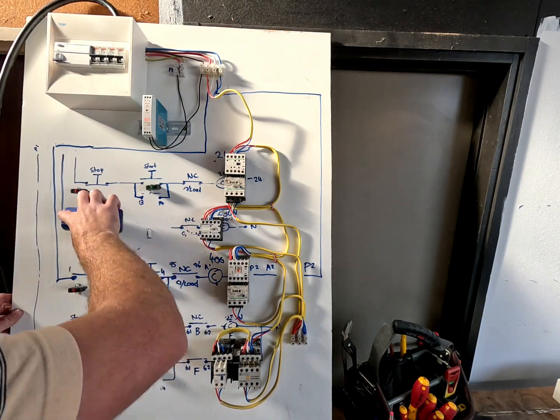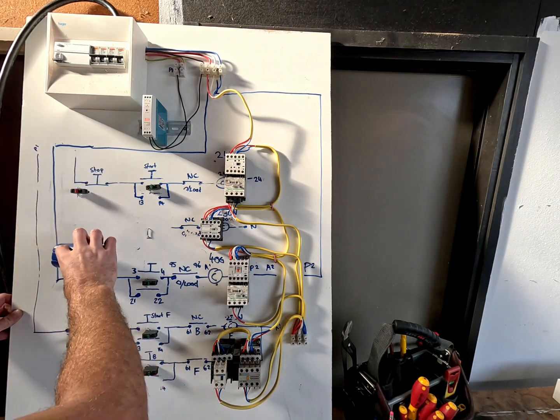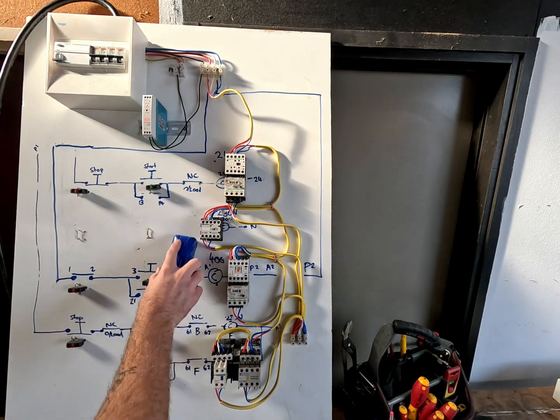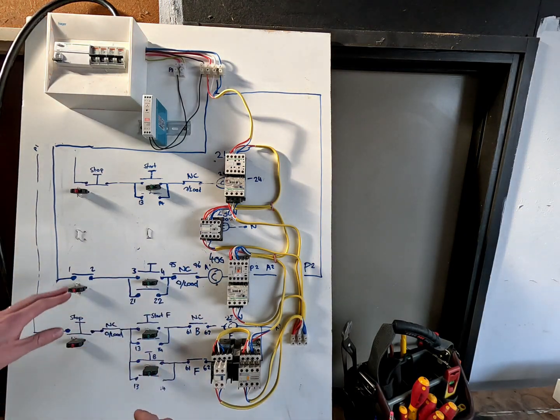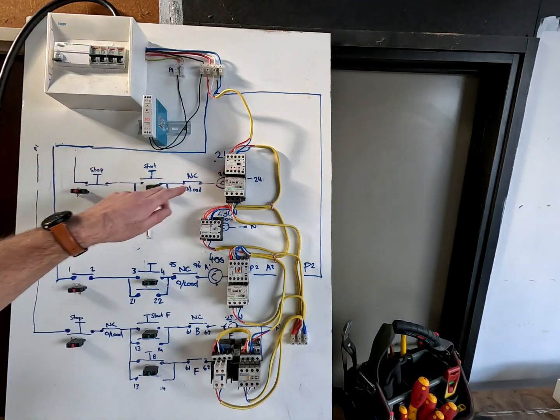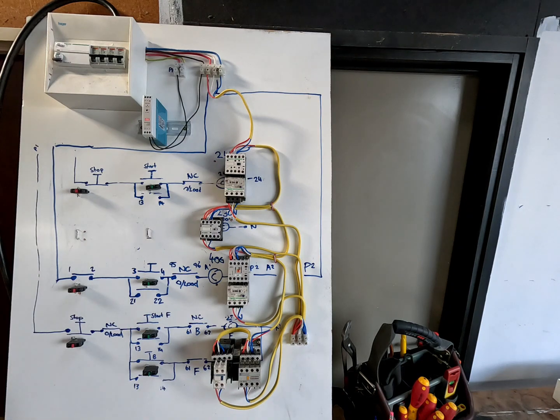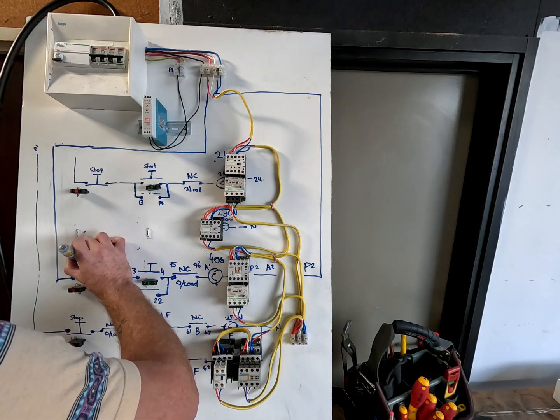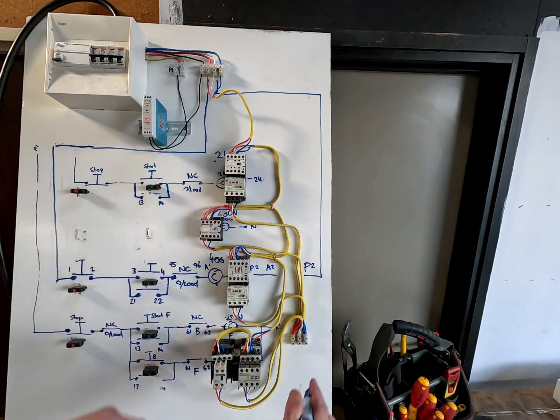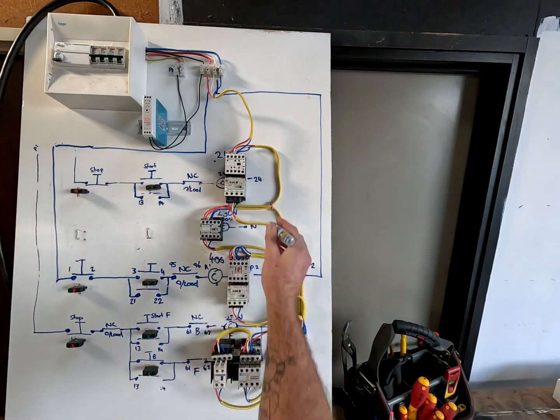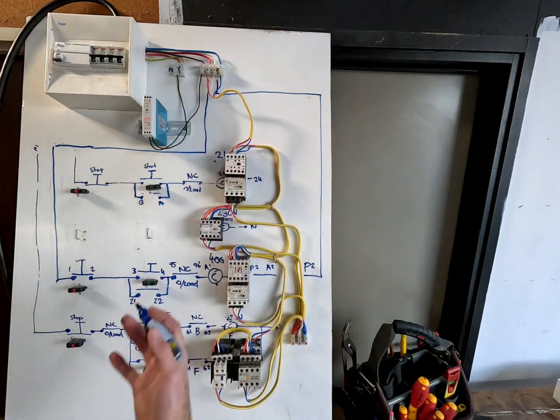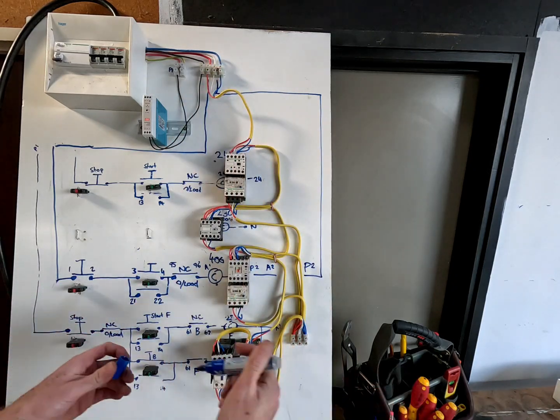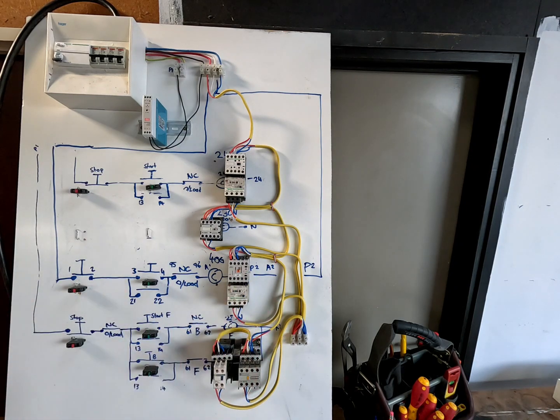The thing that you've got to not get confused about is, as you can see, this is our 24 volt contactor. The diagram is exactly the same because the only thing that's actually changing is this is three phase and this is not, which means the only difference is this goes back to a neutral or a negative, this goes back to the second phase. Otherwise the control circuit is just exactly the same. I'll wire it up, we'll take it over, plug it in, and I'll show you it operating.